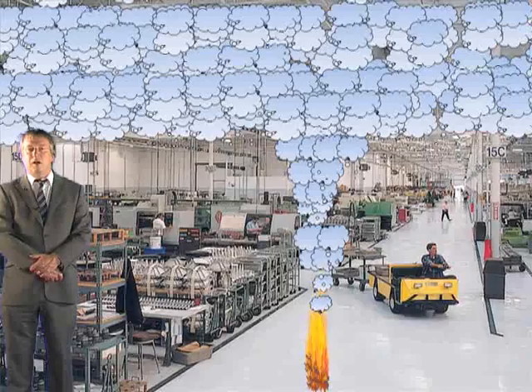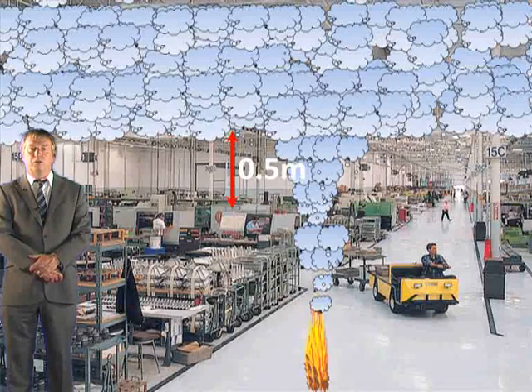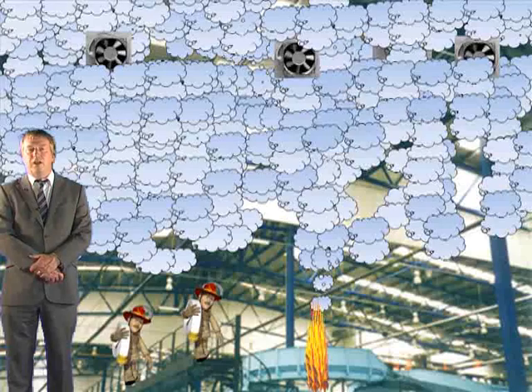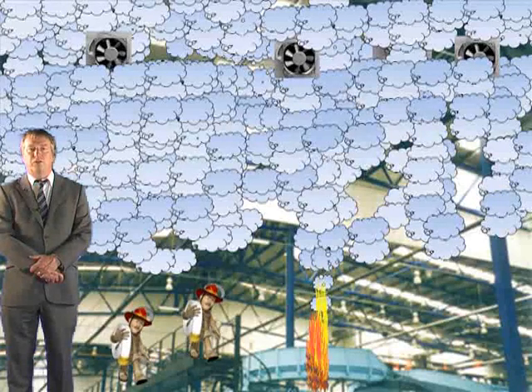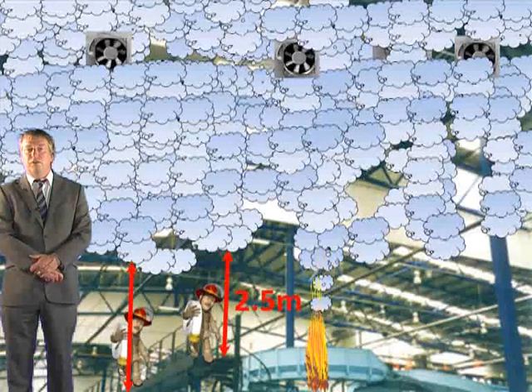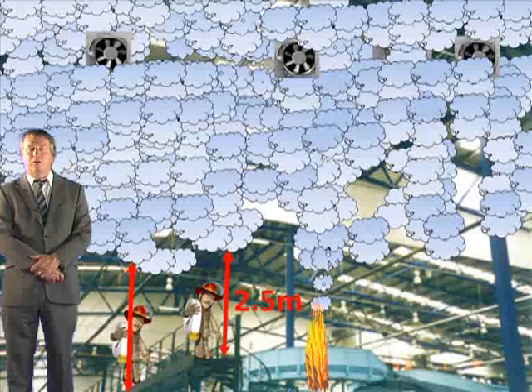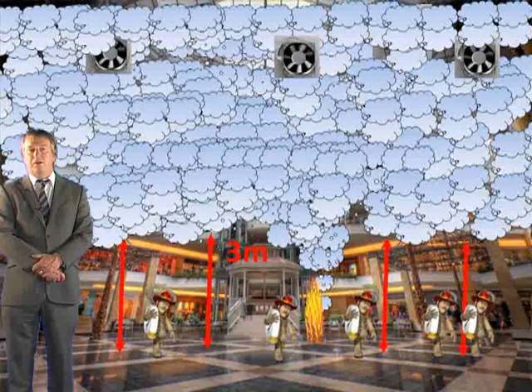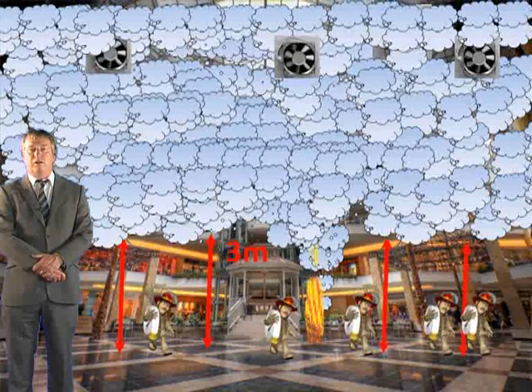Let's look at some examples of design objectives. As an example, the design objective for a warehouse could be to maintain the smoke layer half a metre above the highest stored goods until the fire brigade arrive. In a warehouse with a mezzanine floor, the design objective could be to maintain a clear layer height of 2.5 metres above the heads of the occupants on that mezzanine floor. In a shopping complex, the design objectives might be to maintain a clear layer height of 3 metres above the heads of any members of the public.